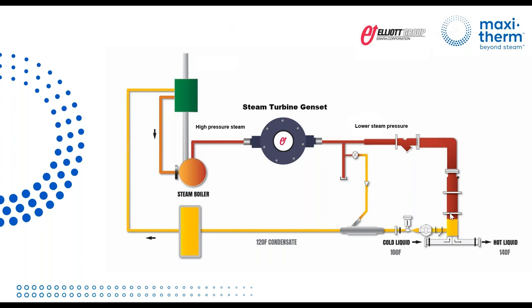Using a flooding design, which will create a 100% closed loop for a new building, for example, or even for a retrofit. The concept, of course, is that you need to create a differential pressure through the turbine. So with higher steam pressure you can come in, and with lower steam pressure you can come out. With the flooding design, if the steam pressure inlet is higher than your condensate back pressure outlet, you don't need a condensate pump. This would be the receiver pump, to go back into the boiler. And when you have a 100% closed loop, if you put a condensing stack economizer here, like they do at Duke University, you'll increase the boiler efficiency.